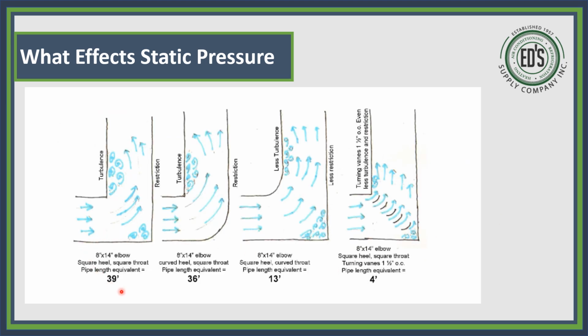So we look at the equivalency of ductwork. Now, here's something I'm going to blow your mind with, because ICP wants you to have 100 feet total ductwork. That's trunk line and flexes, altogether 100 feet. So if I took a 90 with a square throat, square heel, and no turning vanes, look what it's equivalent to: 39 feet of ductwork.